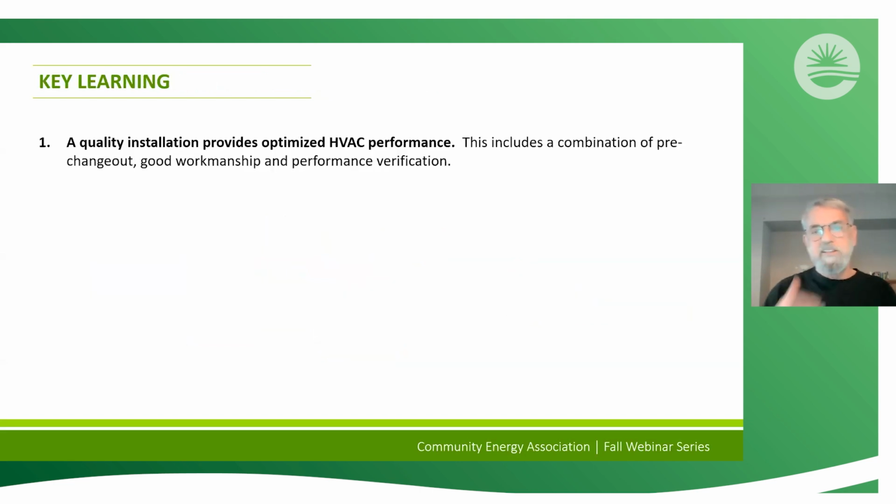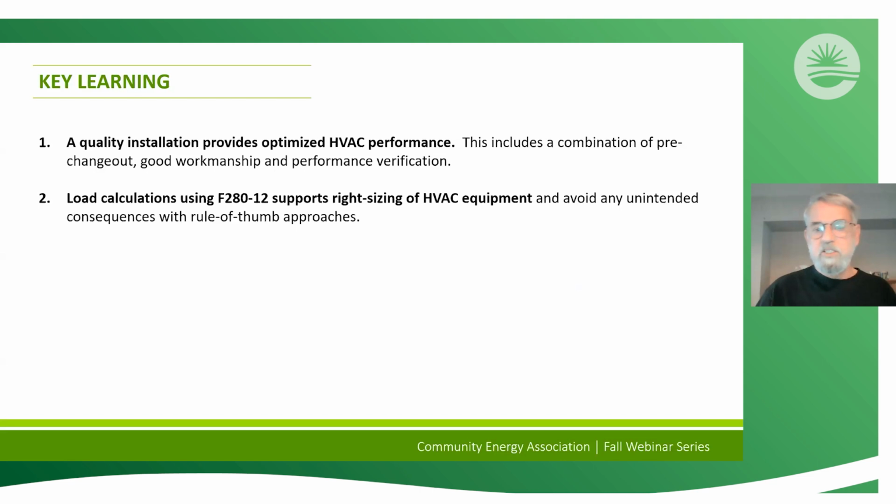What did we learn? I'm guessing on your behalf whether you learned anything at all, but what you were supposed to is quality installation provides optimized HVAC performance, right? That includes a good combination of pre-changeout, good workmanship, and performance verification. Load calculations using F280-12 supports right sizing of HVAC equipment and avoids unintended consequences that come with rule of thumb.